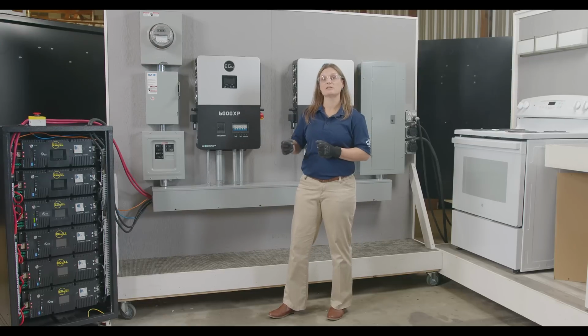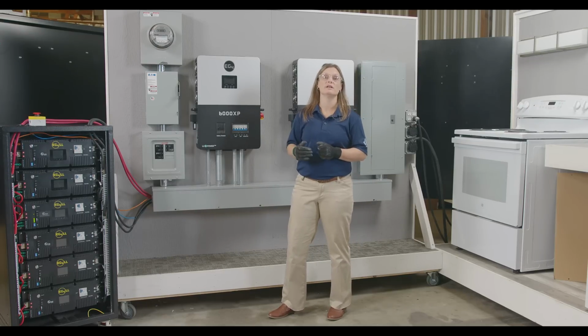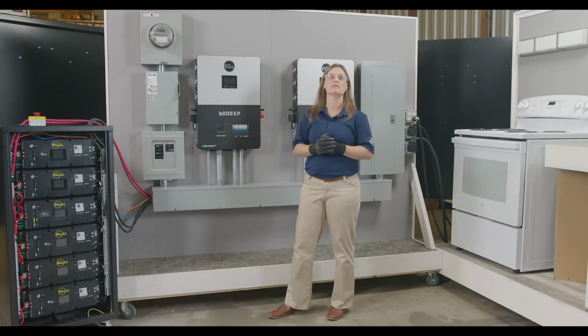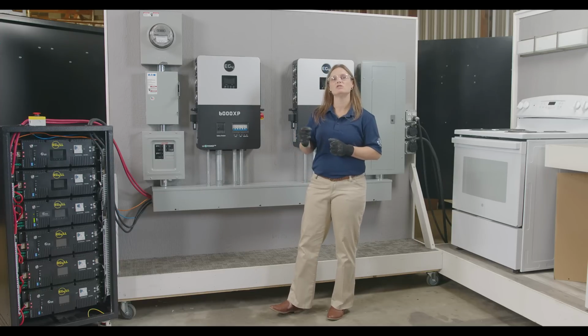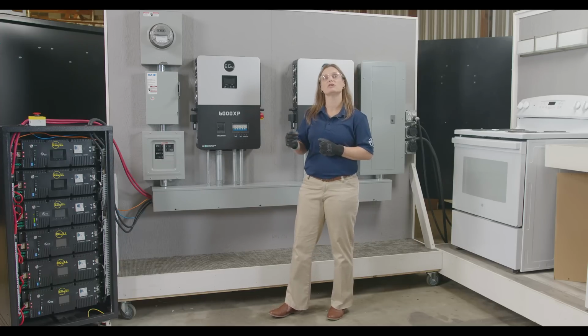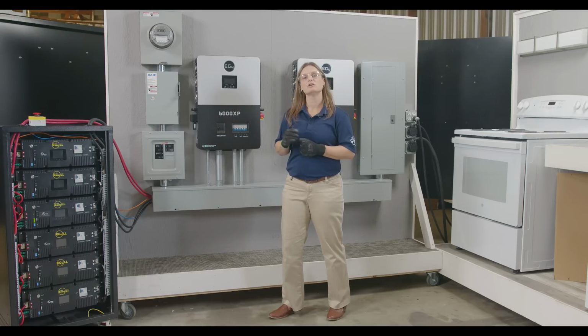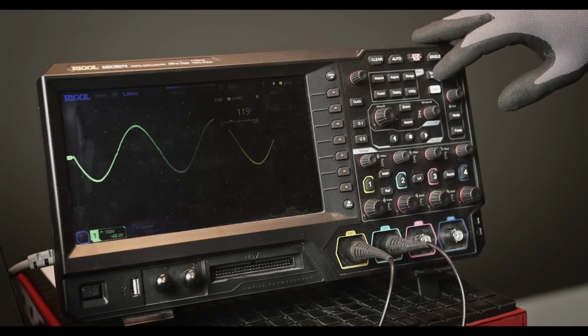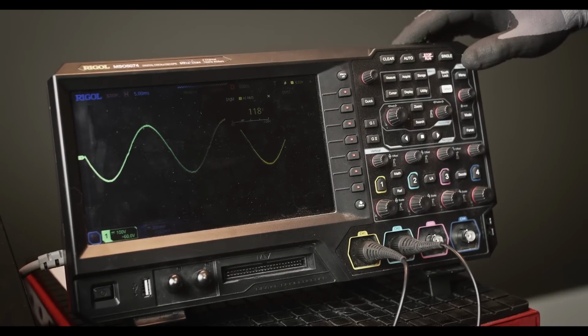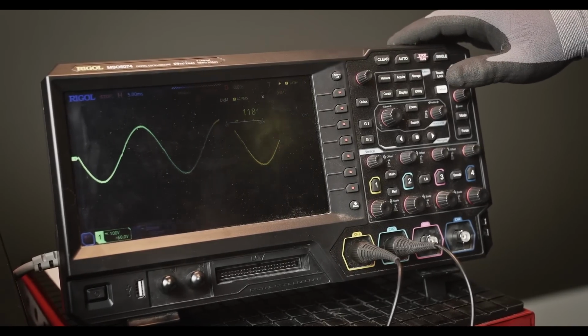The 6000XP inverter works great off-grid. No utility or generator needed. But for a full off-grid living, think about 8 to 12 kilowatt diesel generator for cloudy days. The inverter has a 30 amp AC bypass, so make sure your generator's continuous output ability is larger than that to keep the sine wave as stable as possible.